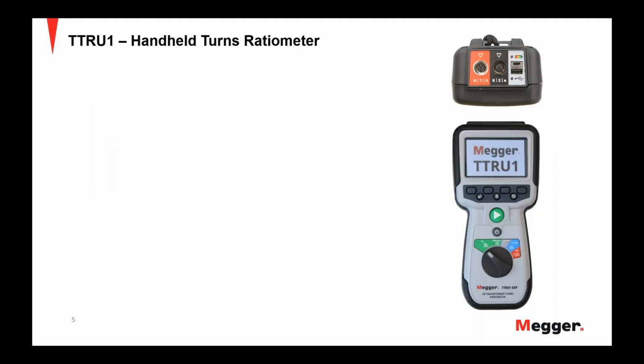Looking at a few of the features of the TTRU1, the first is the full color high bright display. As with most instruments that come out today, we are moving away from the old yellow backlit displays to something that can be more informative. And the way we use that in the TTRU display, the vector group of the transformer that you're going to test directly on screen along with the connections. In the past, you may have required a sort of cheat sheet that told you how to connect to certain transformers, but now we've incorporated that into the instrument itself.